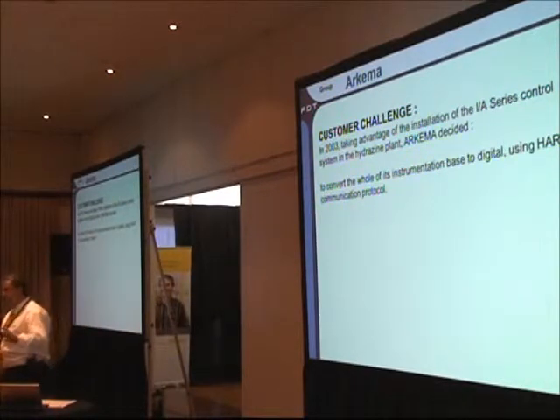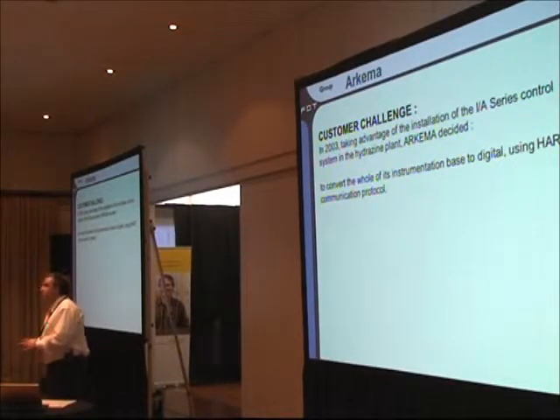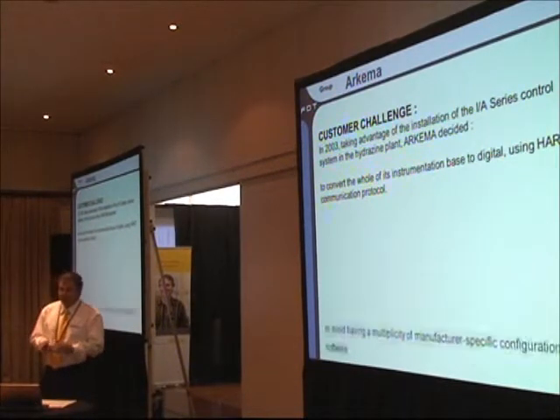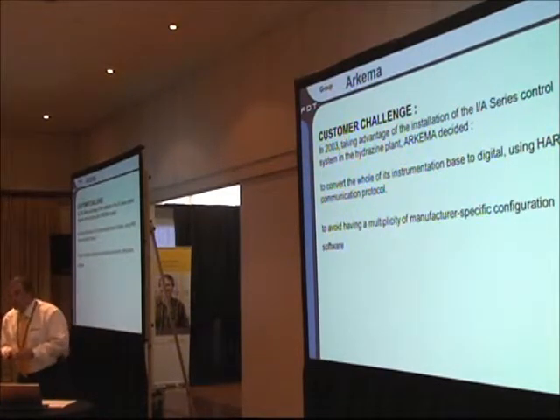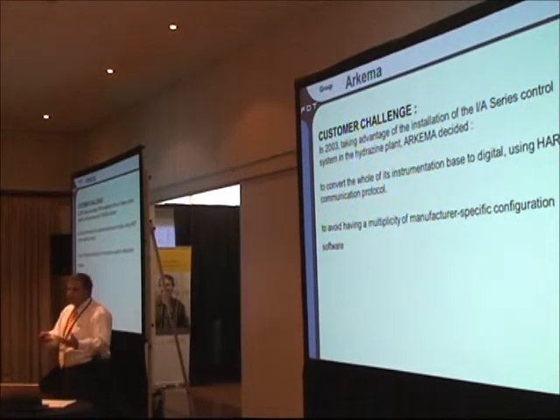HART devices were already installed in the plant, and now they wanted more information from the devices, since before it was a bit poor with only 4 to 20 milliamps. They wanted a step further, and they also wanted to avoid having a multiplicity of manufacturer-specific configuration tools.